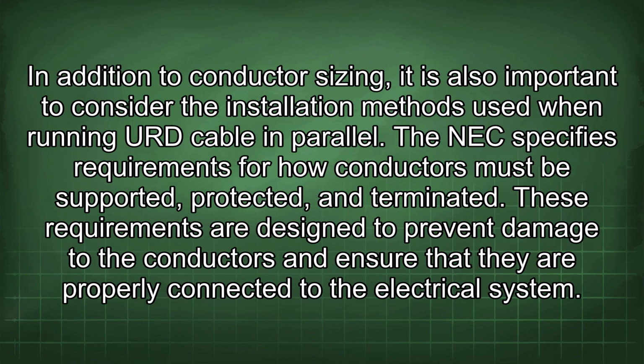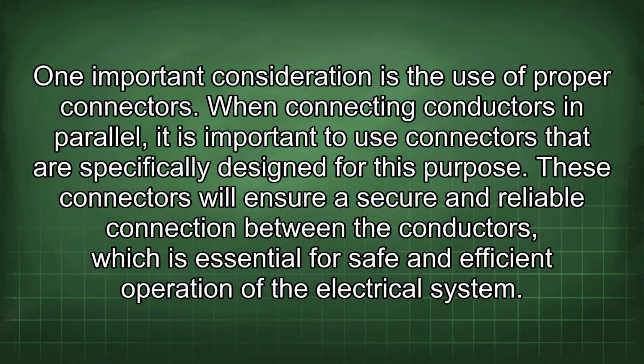In addition to conductor sizing, it is also important to consider the installation methods used when running URD cable in parallel. The NEC specifies requirements for how conductors must be supported, protected, and terminated. These requirements are designed to prevent damage to the conductors and ensure that they are properly connected to the electrical system. One important consideration is the use of proper connectors. When connecting conductors in parallel, it is important to use connectors that are specifically designed for this purpose. These connectors will ensure a secure and reliable connection between the conductors, which is essential for safe and efficient operation of the electrical system.